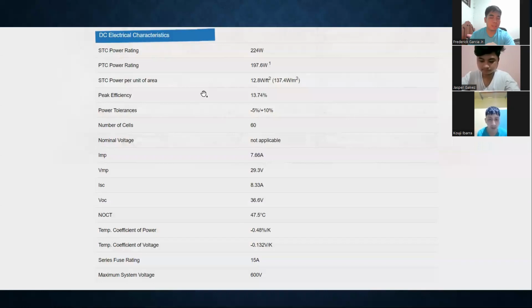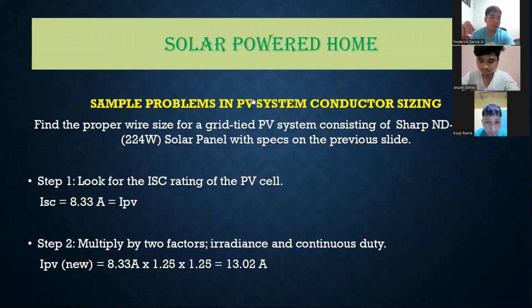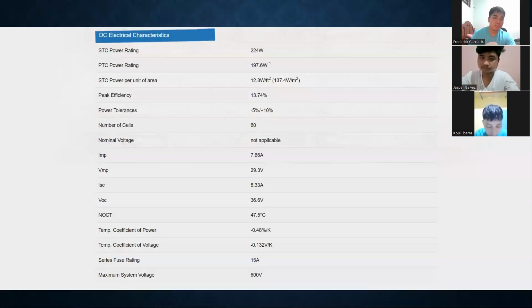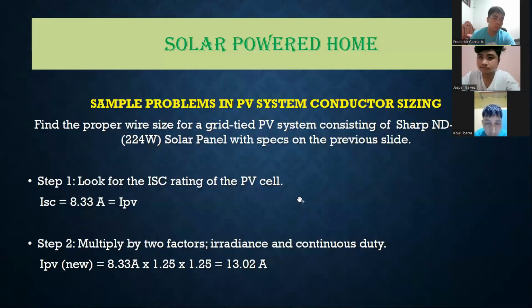Here I have a Sharp ND224UC1 224 watt solar panel's specifications. Here we see that the ISC is 8.33 amps. So for step 1, we take that 8.33 amps and take note of that as the IPV. For step 2, we multiply by the 2 factors. So the IPV new is 8.33 times 1.25 times 1.25, which is equal to 13.02 amps. We'll take note of that 13.02 amps.